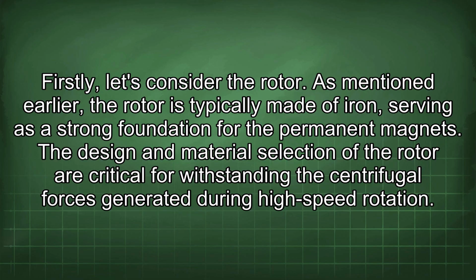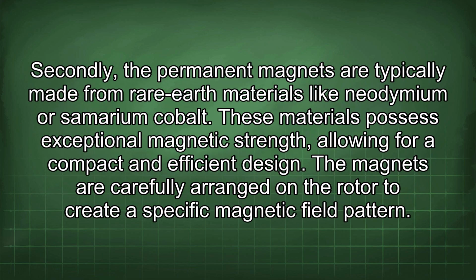Firstly, let's consider the rotor. As mentioned earlier, the rotor is typically made of iron, serving as a strong foundation for the permanent magnets. The design and material selection of the rotor are critical for withstanding the centrifugal forces generated during high-speed rotation. Secondly, the permanent magnets are typically made from rare earth materials like neodymium or samarium cobalt. These materials possess exceptional magnetic strength, allowing for a compact and efficient design. The magnets are carefully arranged in the rotor to create a specific magnetic field pattern.